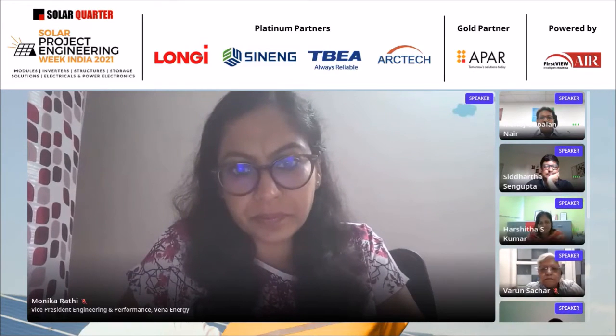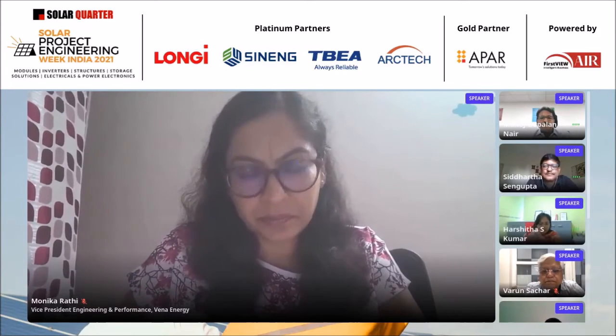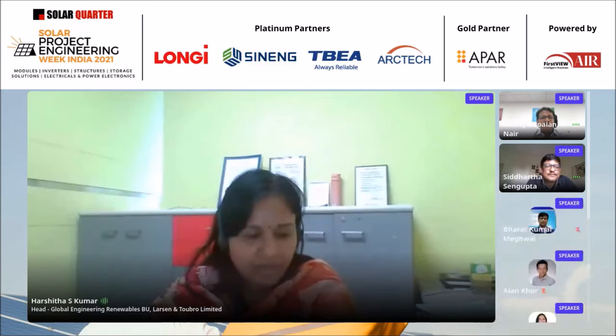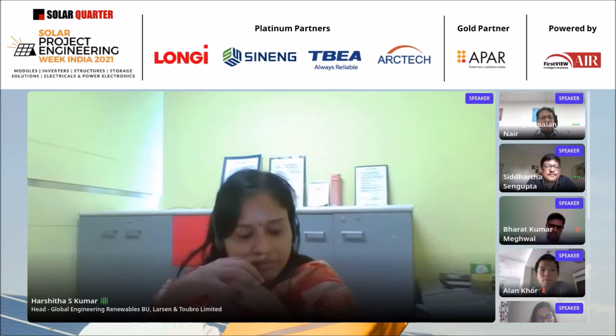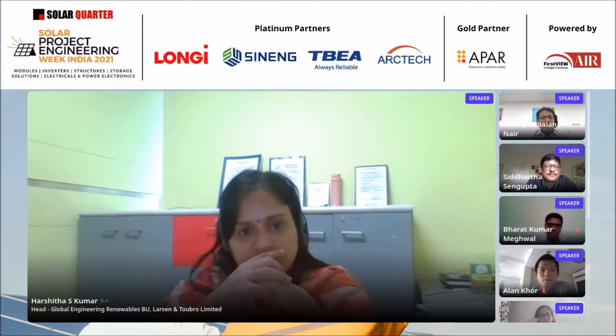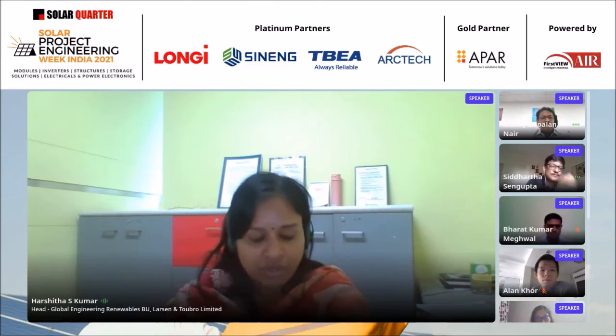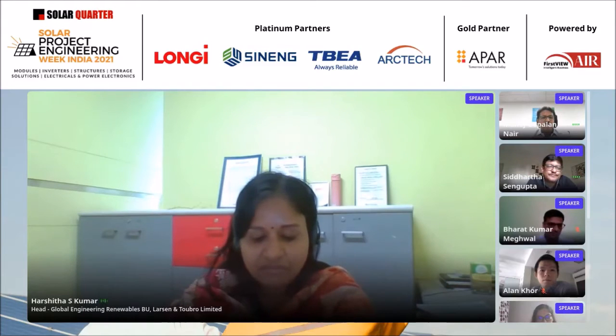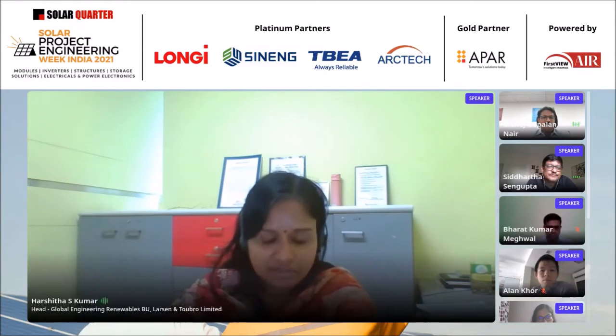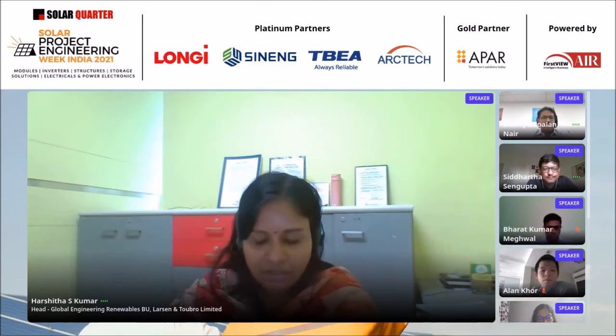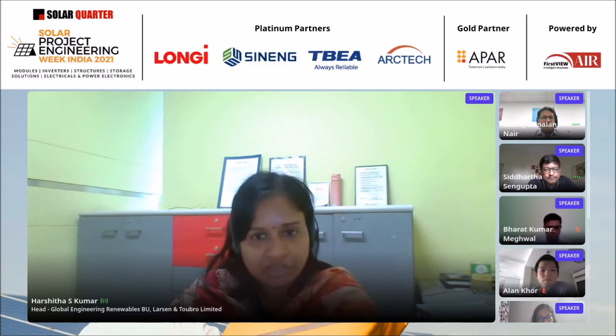Yeah, sure, Monica, and nice to meet you again in this forum. While we look at the compatibility between the modules and inverters, I think already Mr. Allen had nicely touched upon the issues which we are currently facing with high current, high wattage modules as well. So mainly three things is what we need to check. One is the system voltage. Definitely earlier we were at 1000 volt, now it is 1500 volt. So the module string size will depend on the VOC, and accordingly we have to select such that it does not exceed 1500 volt, because if it exceeds that, then there can be tripping and associated curtailment of generation.